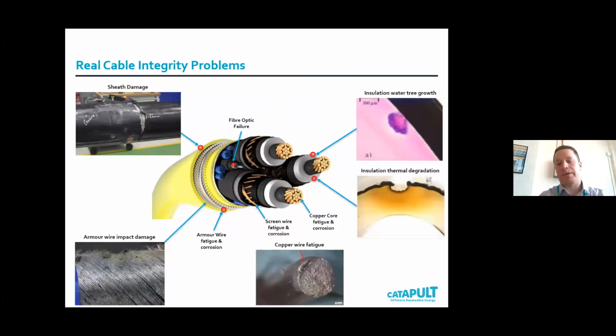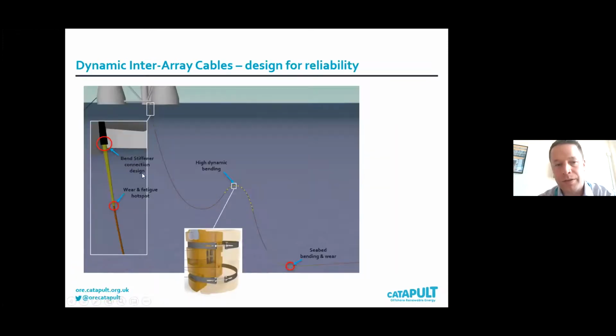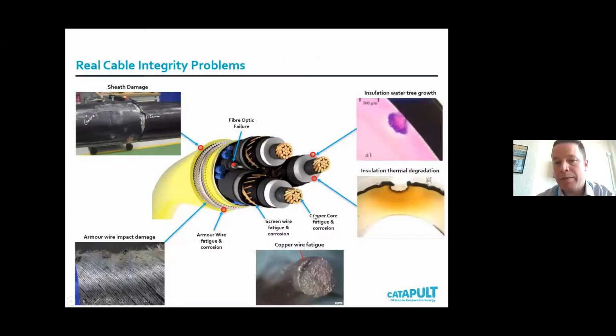And these are some real problems that we've seen on cables. So I think Paul talked about water treeing. So in the insulation itself, if you get too much water and in certain conditions, you can get water tree growth. If you haven't designed the cables properly thermally, you can get some thermal issues. If we go back to this, particularly around the J tube or areas where you've got lots of insulation, or if the cable's in air, there can be too much heat buildup in the cable, and you can get some thermal degradation or overheating.